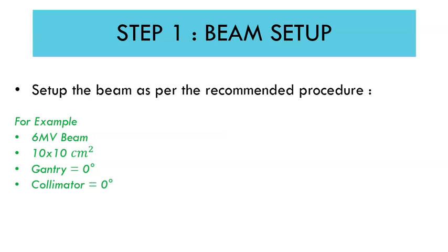Step number one is to do the beam setup. As we saw in the previous slide, set the beam with the gantry zero, collimator zero, 6 MV beam, field size 10 by 10.